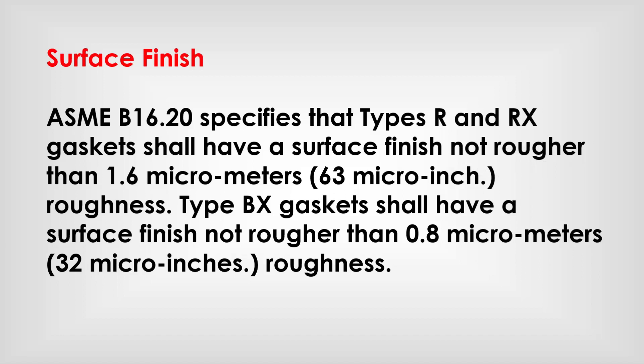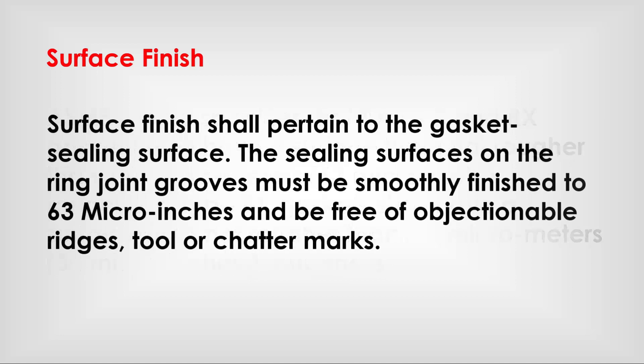Surface finish: ASME B16.20 specifies that Types R and RX gaskets shall have a surface finish not rougher than 1.6 micrometers roughness, and type BX gaskets shall have a surface finish not rougher than 0.8 micrometers roughness. The sealing surfaces on the ring joint groove must be smoothly finished to 63 micro-inches and be free of objectionable ridges or tool marks.